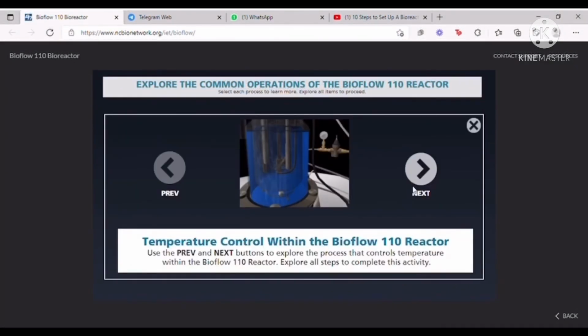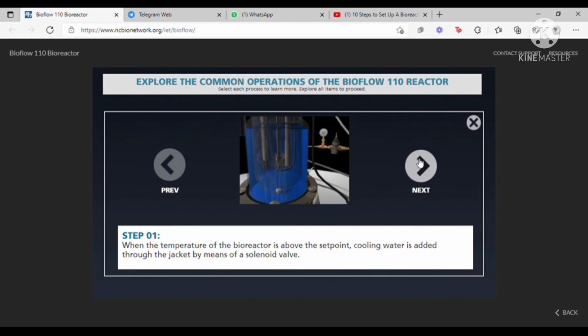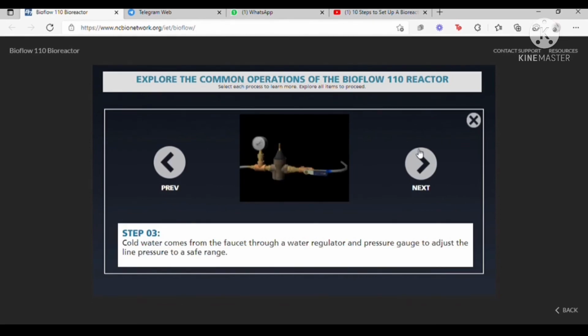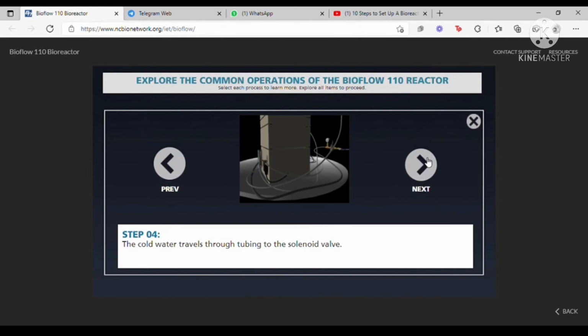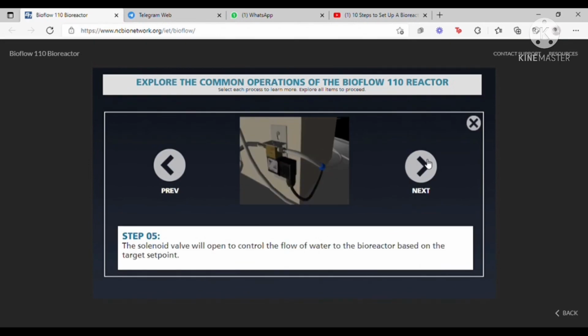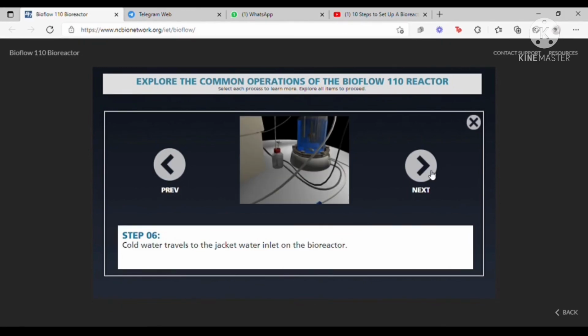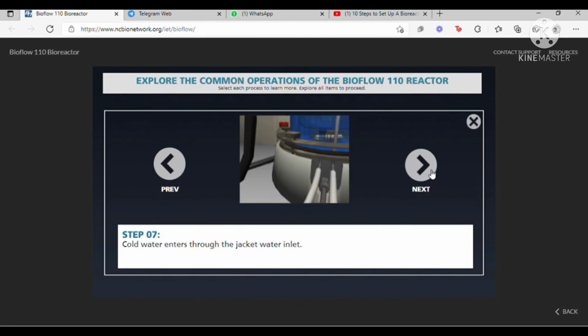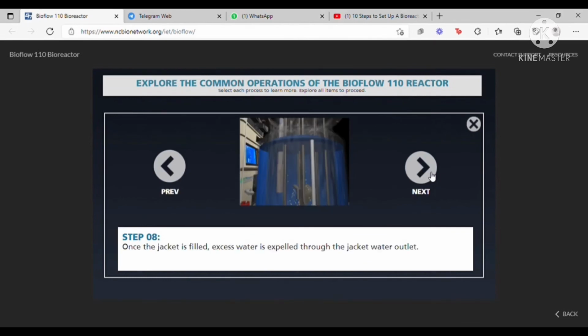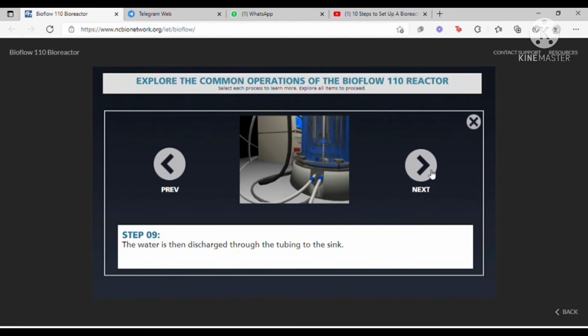Next is process 5, which is temperature control. Step 1. When the temperature of the bioreactor is above the set point, cooling water is added through the jacket by means of a solenoid valve. Next, when the temperature is below the set point, the jacket water heater comes on to heat the jacket water. Cool water comes from the faucet through a water regulator and pressure gauge to adjust the line pressure to a safe range. Cold water travels through the tubing to the solenoid valve. Step 5. The solenoid valve will open to control the flow of the water to the bioreactor based on the target set point. Step 6. Cold water travels to the jacket water inlet on the bioreactor. Next, the cold water enters through the jacket water inlet. Once the jacket is filled, excess water is expelled through the jacket water outlet. Step 9. The water is then discharged through the tubing to the sink.